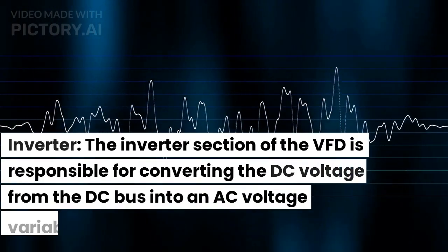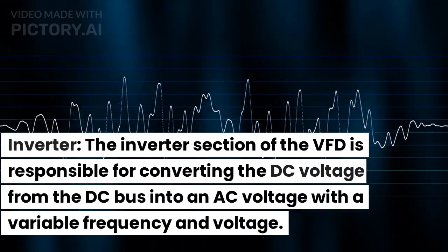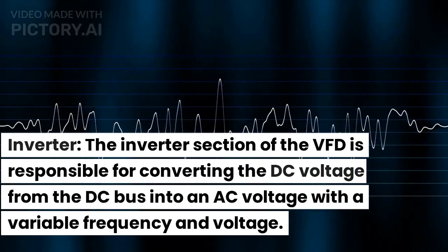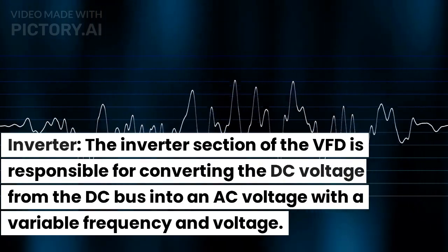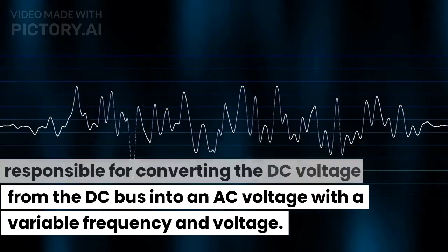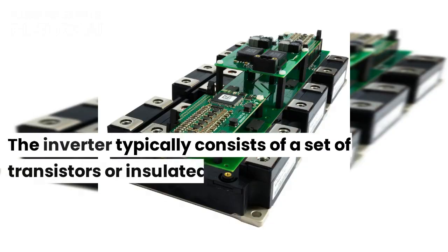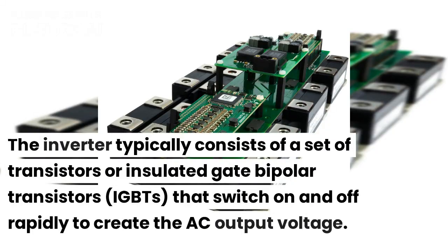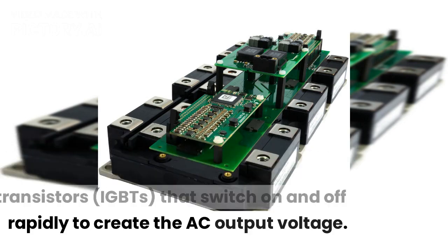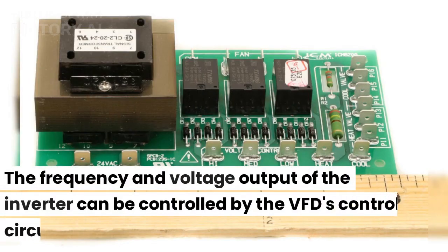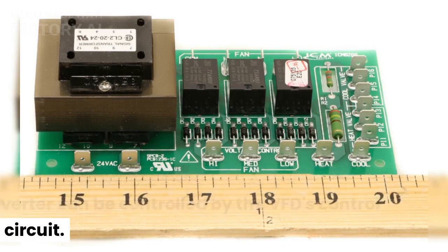Inverter. The inverter section of the VFD is responsible for converting the DC voltage from the DC bus into an AC voltage with a variable frequency and voltage. The inverter typically consists of a set of transistors or insulated gate bipolar transistors, IGBTs, that switch on and off rapidly to create the AC output voltage. The frequency and voltage output of the inverter can be controlled by the VFD's control circuit.